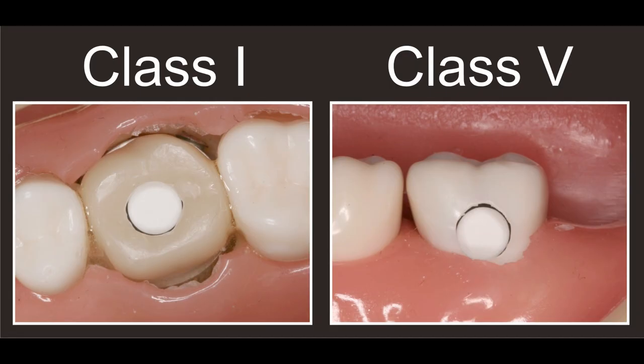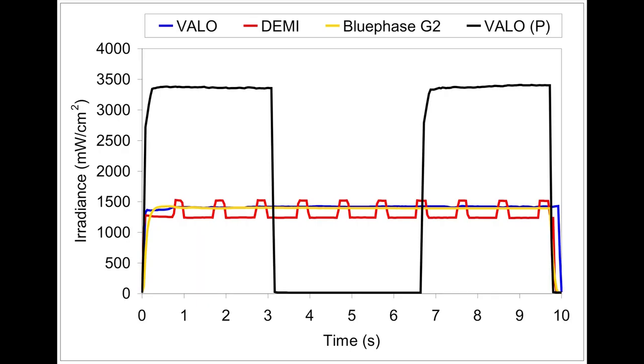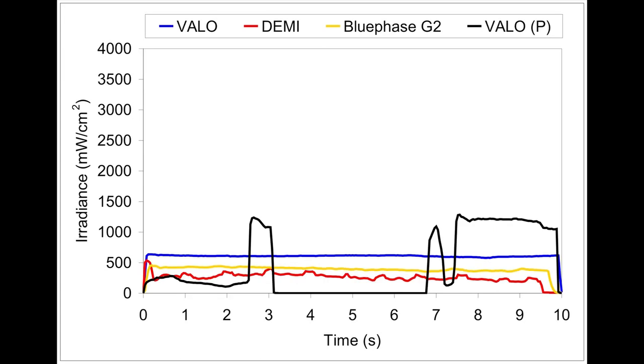Here we can see the location of the sensors described in the article. The sensor in the Class I location was 4 mm from the cusp tip and in the Class V location the sensor was 2 mm from the facial surface. One example shows an operator who used the curing light to its maximum potential, delivering a very uniform irradiance in the Class V location. By contrast, another operator was less steady and delivered a very non-uniform and low amount of energy to the Class V detector.